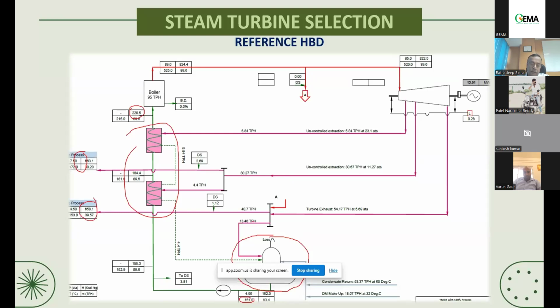Also, this is the exhaust from the turbine, which is a back pressure turbine, I am taking to the deaerator, and from this extraction only I am giving to the process. I have taken another extraction here to enhance further. So this may or may not be required. That cycle analysis has to be done, whether you can use a HP heater or not. Even if you do not have this extraction requirement, still you should have at least one HP heater in the system when your megawatt is around 13 to 20 megawatt. And if you go beyond 25-30 megawatt, you should have at least two HP heaters.